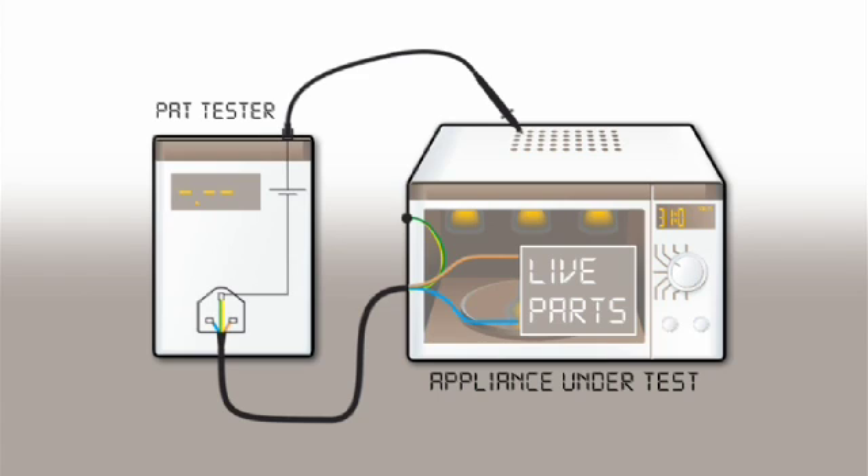As we can see, the appliance is plugged into the PAT and the test probe is connected to exposed metal parts. Current is then passed from the PAT tester through the protective earth conductor of the mains cord to the enclosure, and then flows back to the PAT tester via the test lead. The PAT will then display the resistance of the protective earth path.